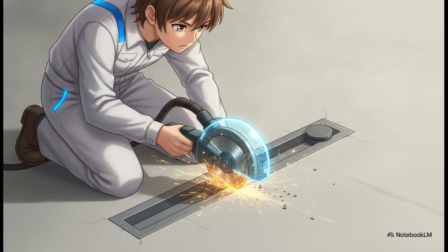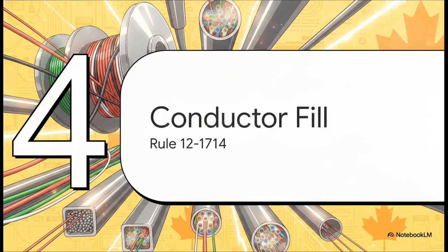The whole goal here is to prevent sharp little chips of metal from falling in, because those will completely shred your insulated conductors during your wire pull. Honestly, dirt and debris are your absolute worst enemies in a floor raceway system. Moving right along to Section 4, Conductor Fill.